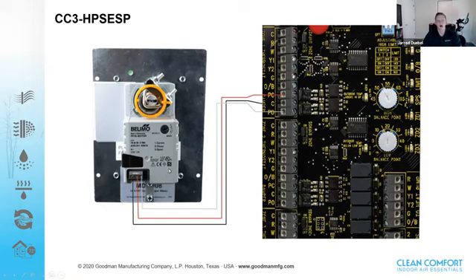they actually have about a 2.5 VA draw per zone damper. So we typically say, rule of thumb, you don't really want to exceed 30 VA draw per zone. You can in specific instances, but we always suggest getting engineering involved if you're going to exceed that. So at 2.5 VA per damper, 30 VA per zone, we can put quite a few dampers on a specific zone. So oftentimes you're never going to need to put more than 4, 5, 6 dampers, but we can get upwards of 10 to 15 dampers per zone.